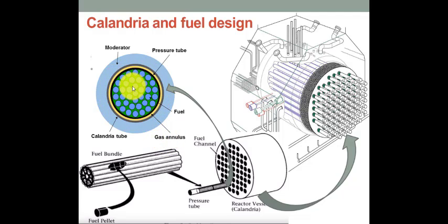This is the first layer of the containment, and above this layer there is the pressure tube and then the calandria tube, and the pressure tube is inserted here, over which the heavy water circulates in the system. In conventional design with a pressurized core, refueling requires the core to shut down and the pressure vessel to be opened. Due to the arrangement used in the CANDU reactor, only the single tube being refueled needs to be depressurized. This allows the refueling of the CANDU reactor without shutting down.